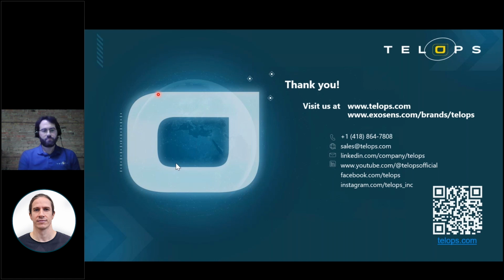One mitigation possible, if you have mixes of gases that are spectrally overlapping and you know the right ratio of these gases, is to create a custom signature, because with our system you can not only detect gas with a pre-existing library that we publish, you can also create your own signature. And if you create a custom signature, which is the mix of the two gases that you're looking for, then you can detect it with your new algorithm with no problem. Good point.